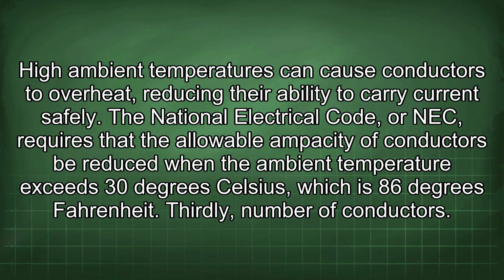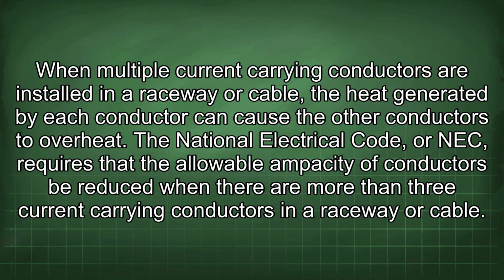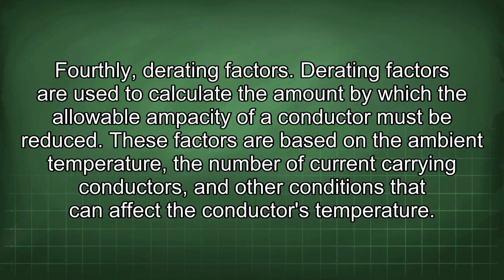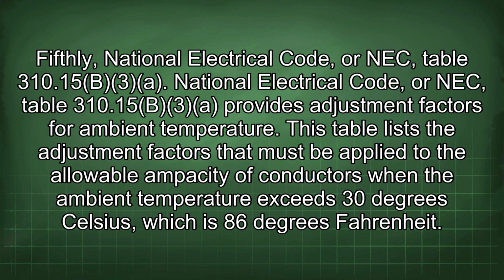Thirdly, number of conductors. When multiple current-carrying conductors are installed in a raceway or cable, the heat generated by each conductor can cause the other conductors to overheat. The National Electrical Code, or NEC, requires that the allowable ampacity of conductors be reduced when there are more than 3 current-carrying conductors in a raceway or cable. Fourthly, derating factors. Derating factors are used to calculate the amount by which the allowable ampacity of a conductor must be reduced. These factors are based on the ambient temperature, the number of current-carrying conductors, and other conditions that can affect the conductor's temperature.